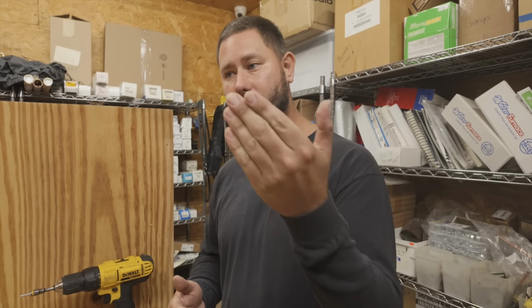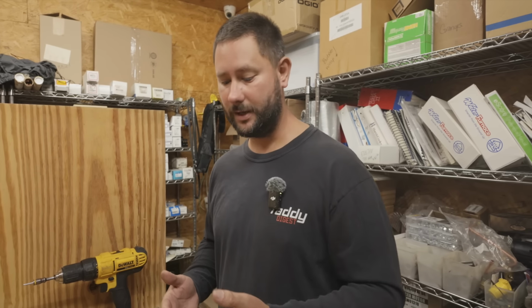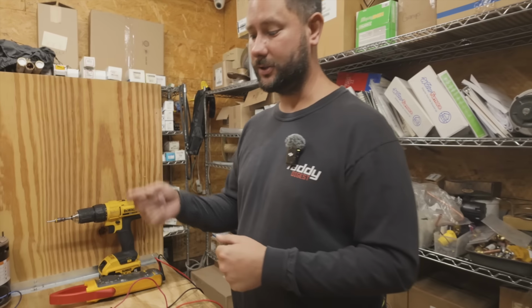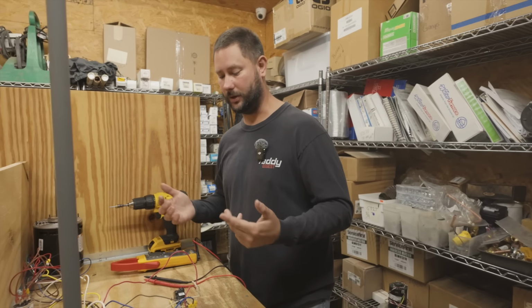Now let's test the blower control board or the blower time delay relay board. Now this board's a little bit different than a typical relay because it needs the secondary voltage from the transformer. It doesn't just need C and Y or C and G or C and W. It needs C and R and then Y or G or W. Now we're going to use C and G for this, but I wanted you to know that we also hooked up the R from the secondary of the transformer.